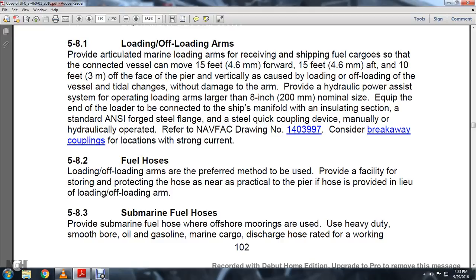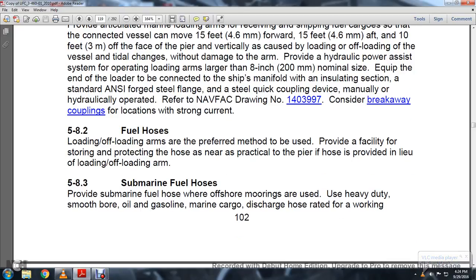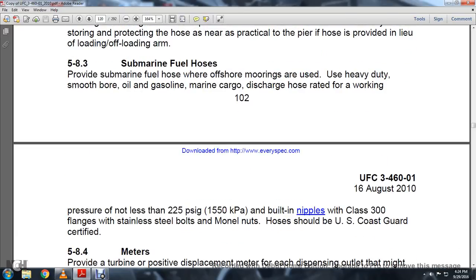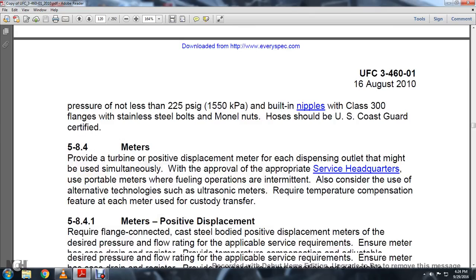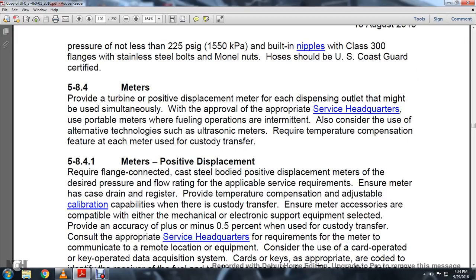5.8.2, fuel hoses. Loading and offloading arms are the preferred method to be used. Provide facilities for storing and protecting the hose as near as practical to the pier, and hoses are provided in lieu of an offloading arm. 5.8.3, submarine fuel hoses. Provide submarine fuel hose where offshore moorings are used. Use heavy-duty smoothbore oil, gasoline, marine cargo discharge hose rated for a working pressure of not less than 225 psi, built with nipples and Class 300 flanges, stainless steel bolts, and Monel nuts. Hoses should be U.S. Coast Guard certified.